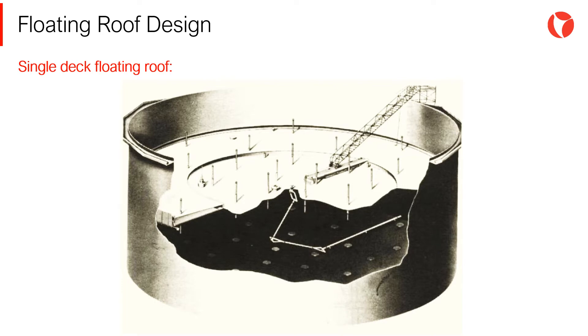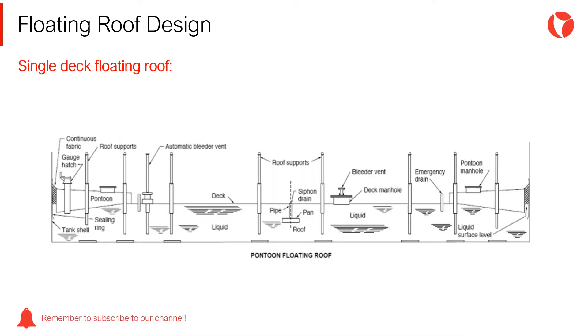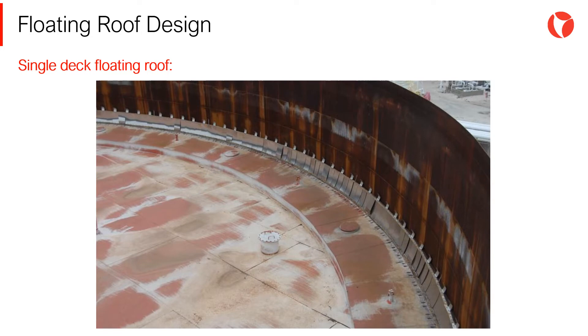Single deck floating roofs consist of a flat central cover surrounded by pontoons — floats — which are divided radially into compartments. Since the roof is exposed to the environment, the design must warranty adequate drainage. The central cover is formed by a membrane made of steel plates, overlapped and welded by means of a fillet weld, usually only in the upper part and connected to the inner part of the pontoon. The different parts of this type of roof are shown on the screen.